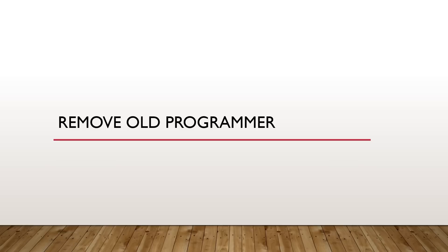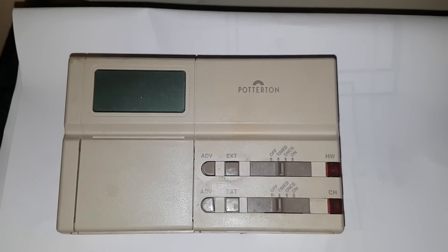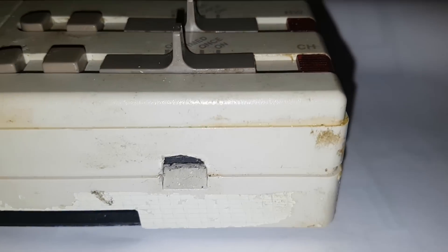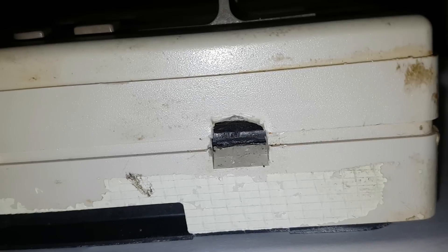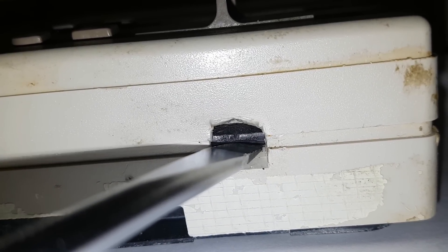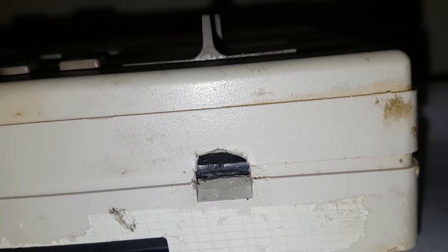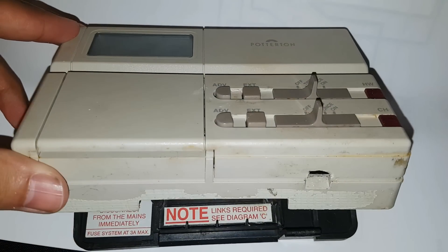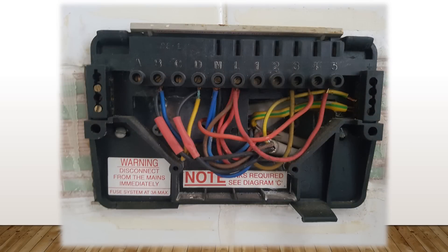So how do we remove the old programmer? This is what my old programmer looks like. There should be a tab somewhere — mine's on the bottom, yours might be on the left or right. Push that tab in as much as you can and then lift it. You'll see the wall plate where all the wires are going. This is what my wall plate looks like with all its terminals. It looks a bit daunting but I'll explain exactly what's going on. The timer we took off has a diagram on it which we need to have a look at.